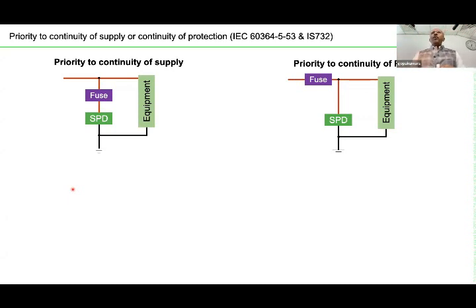So what do you do? You have to have a backup, an additional protection. The purpose of this additional protection is at the end of life of the SPD. It is not for normal condition. At the end of life of the SPD, nobody knows when that is. It may be 2 years, 3 years, 20 years also. At the end of life of this SPD, this backup fuse should protect the entire installation by isolating the SPD safely from the circuit. That is how it is.